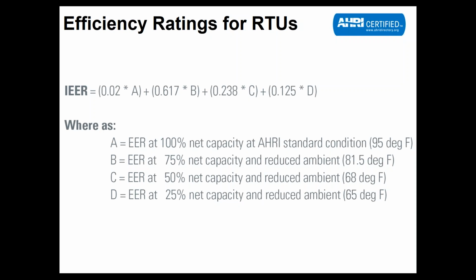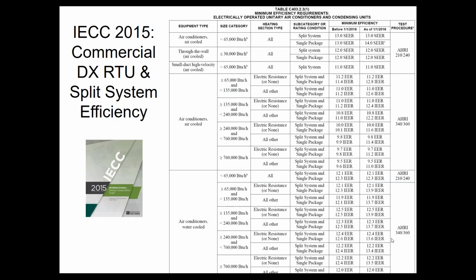And they take those and they weight them. So the 100% only gets a 2% weighting per the formula on top. The 75% testing point gets a 62% weighted bucket. 50% gets a 24, and then 12% on the really low end. So essentially, they're telling you 100% capacity, that efficiency is irrelevant. You need to focus on the mid-tier ranges, 50, 75, and those kind of things.